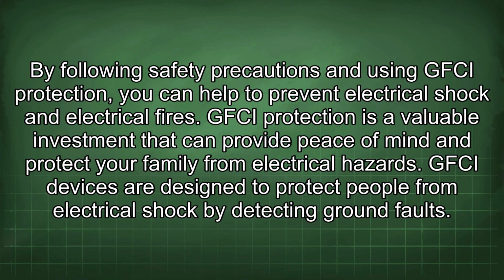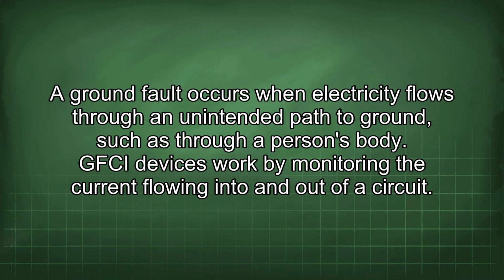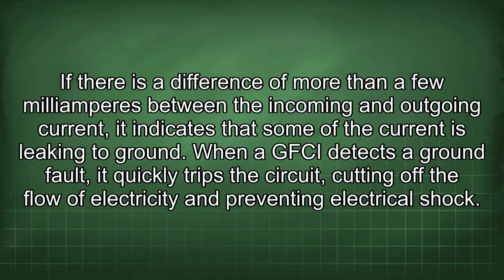GFCI devices are designed to protect people from electrical shock by detecting ground faults. A ground fault occurs when electricity flows through an unintended path to ground, such as through a person's body. GFCI devices work by monitoring the current flowing into and out of a circuit. If there is a difference of more than a few milliamperes between the incoming and outgoing current, it indicates that some of the current is leaking to ground.